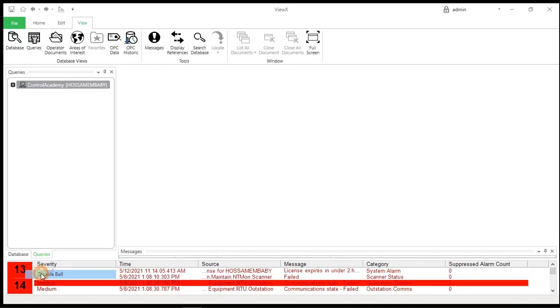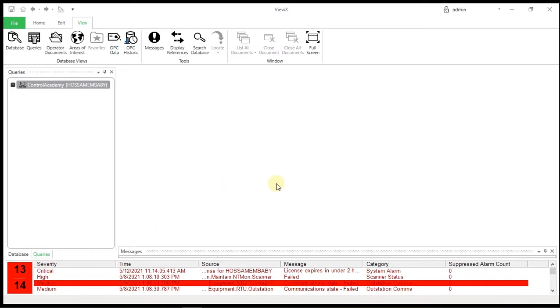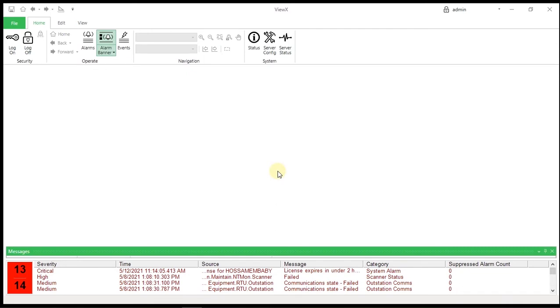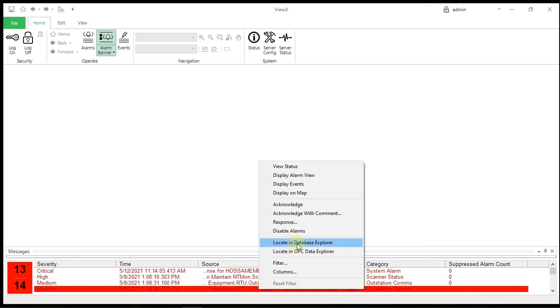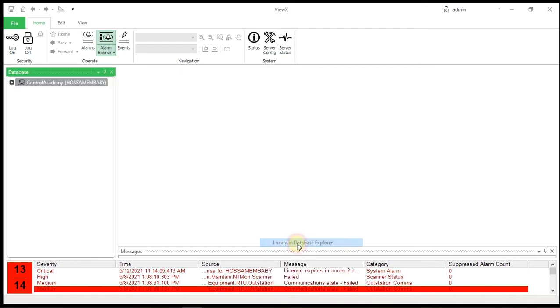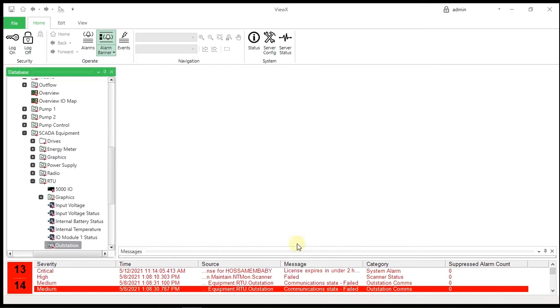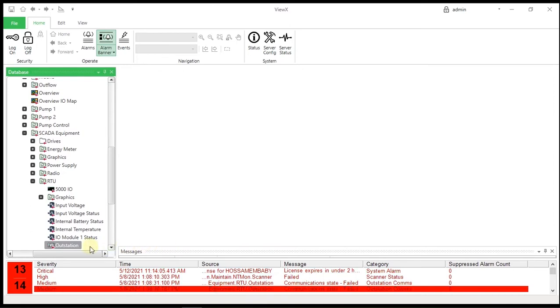Disable the alarm bell by right-clicking on the annunciator and selecting disable the alarm. Now we will right-click the active alarms displayed in the alarm banner. A context-sensitive menu is displayed. Select the locate in database explorer option. The database pane expands automatically, revealing the location of the runtime alarm object with which the alarm is associated. The object is highlighted.